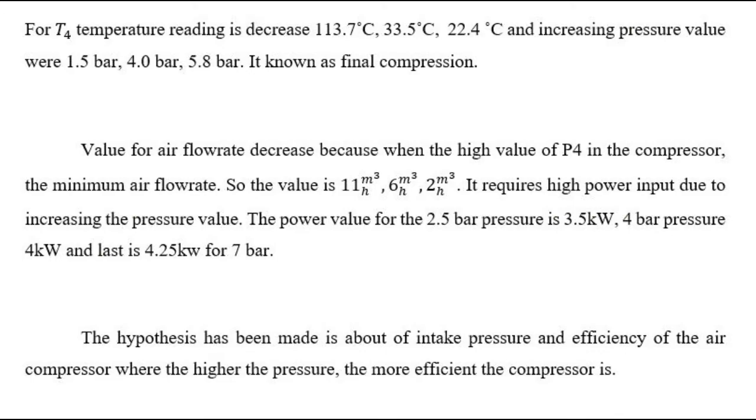It requires high power input due to the increasing pressure value. The power value for the 2.5 bar pressure is 3.5 kilowatt, for 4 bar pressure is 4 kilowatt, and the last is 4.25 kilowatt for 7 bar.